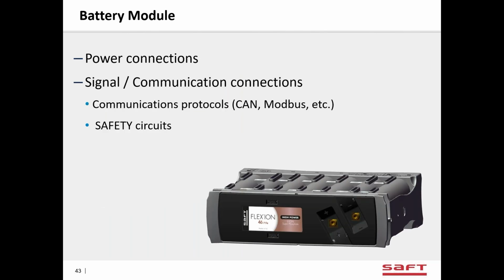This is a picture of the module with the plastics all on. There is a communication from this module to the battery management module so that we can read all of the voltages and temperatures. And this also has the limits in it, safety circuits that are not software dependent. We have hardware comparators that if a cell goes out of range, even if our software is out to lunch, we have hardware protections for over temperature, over voltage, and under voltage built into this circuit board. So it's a level of redundancy for safety.